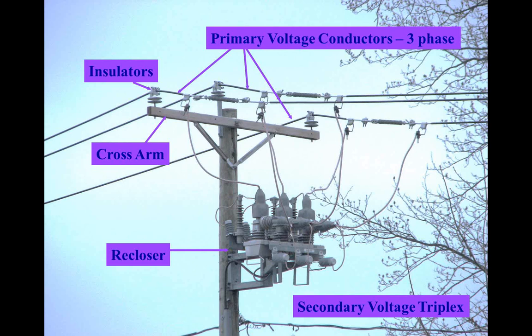Now, the important thing to understand about that: if you've got wire down on the road and you look at it and it's just sitting there and it's burning and burning and it's not going out, the recloser is not seeing enough fault current to cause that thing to trip. It thinks maybe somebody turned on a washer and a dryer and there's a little bit of extra load, but it does not see enough fault current to trip. So if the wire goes out, it's going to try to come back in eventually. So you never trust any wire until the utility person is there, and they're going to take care of it. Nothing you can do about it, nothing you can do to handle it.